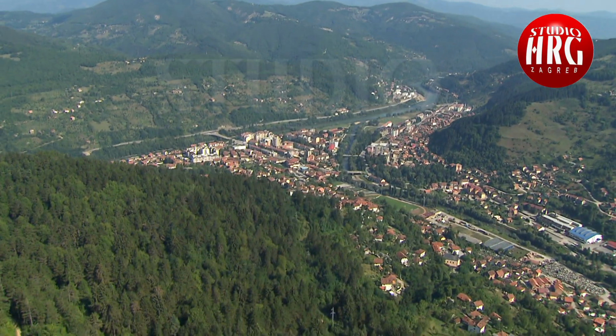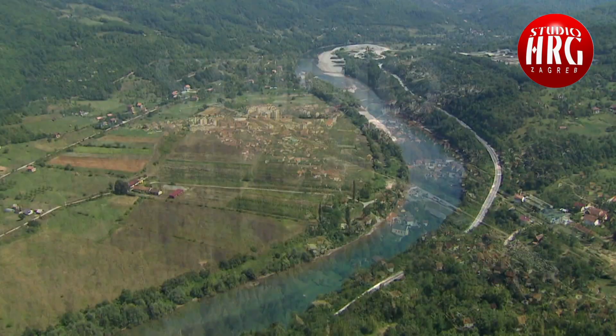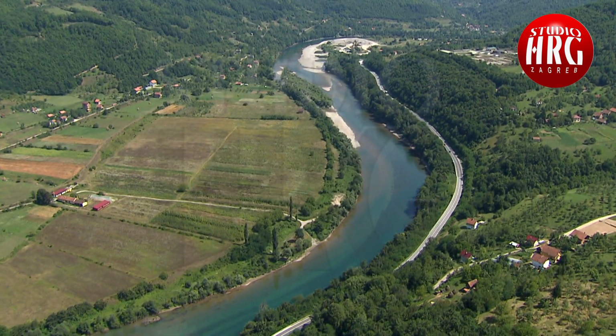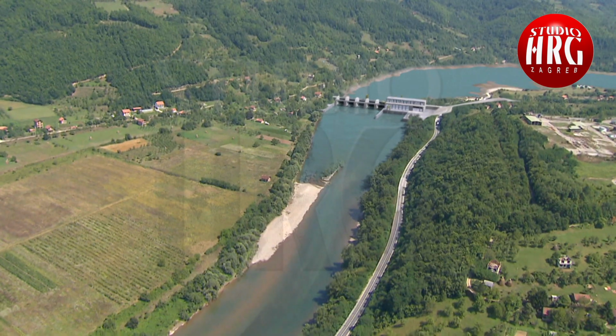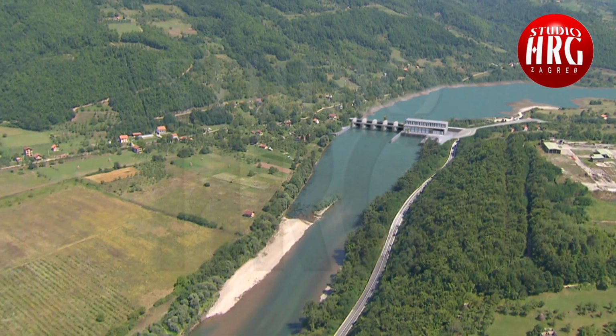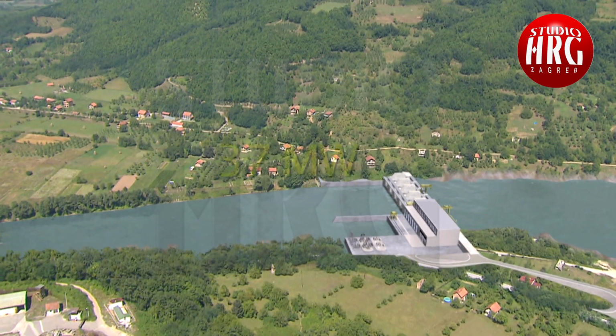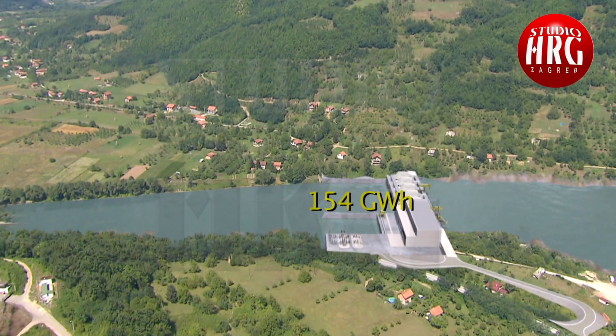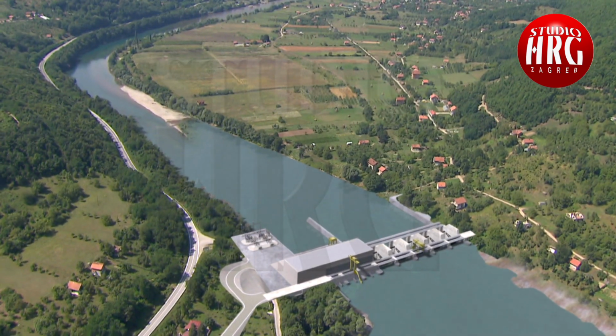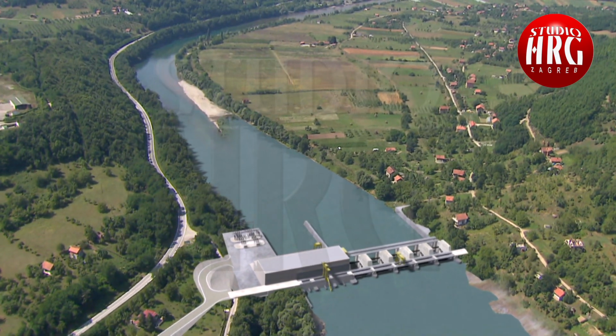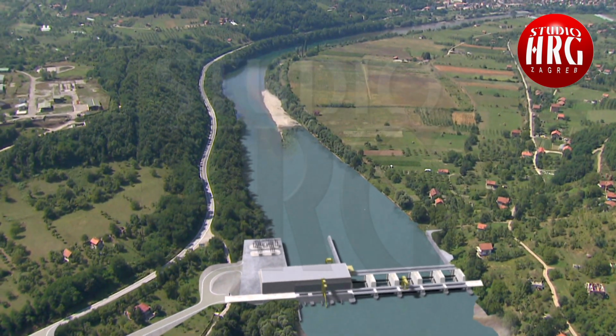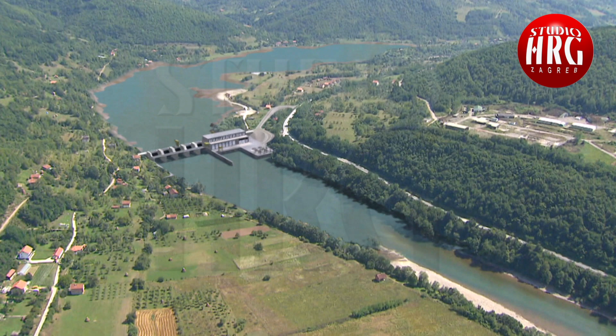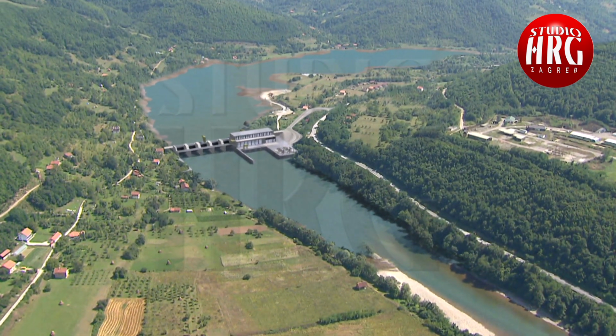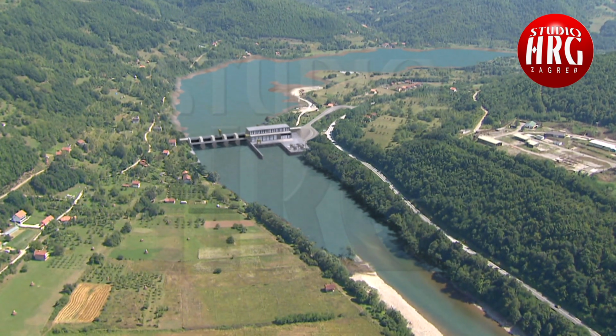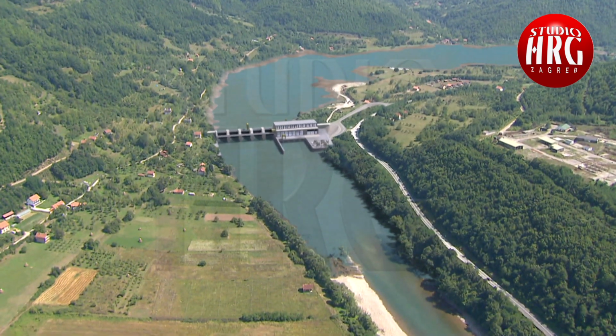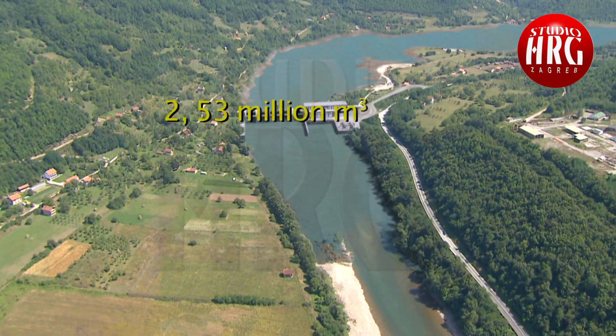Downstream from the town of Focha, at the point where the Chechotina River enters the Drina, 315 kilometers from the confluence of the Drina and Sava, construction is planned for the Paunsi hydropower plant. The facility's installed capacity will be 37 megawatts with a planned annual output of 154 gigawatt hours. The power plant dam will be a concrete gravity-type structure, 250 meters long, with a dam crest elevation of 386 meters above sea level. The dam will create a reservoir with a normal pool elevation of 384 meters above sea level and a useful water capacity of 2.53 million cubic meters.